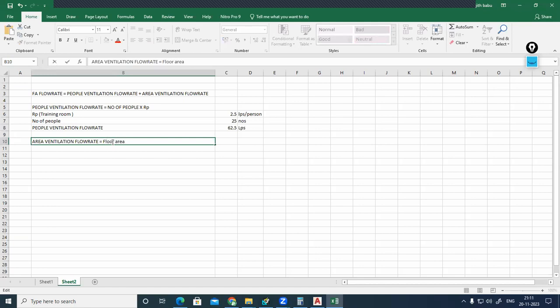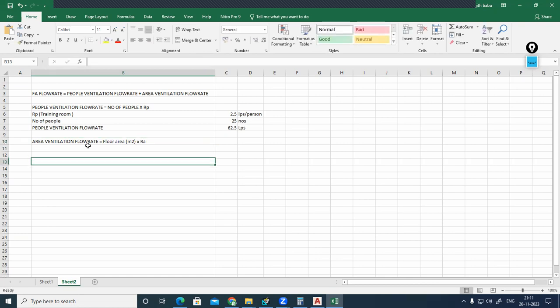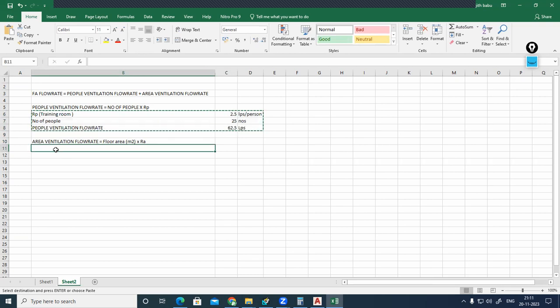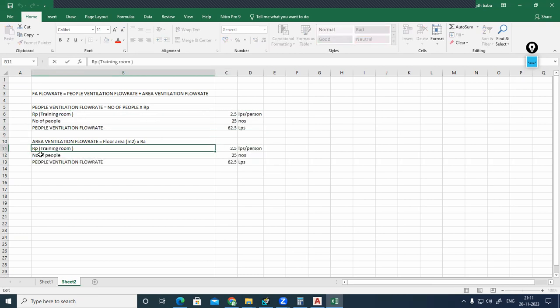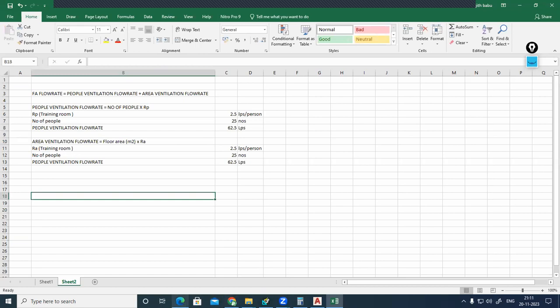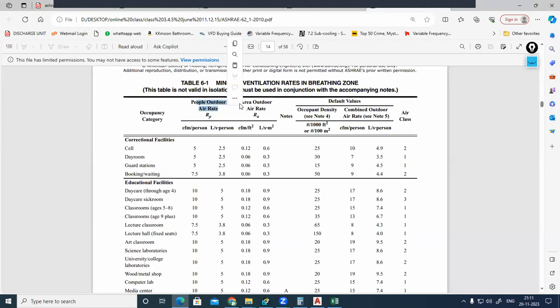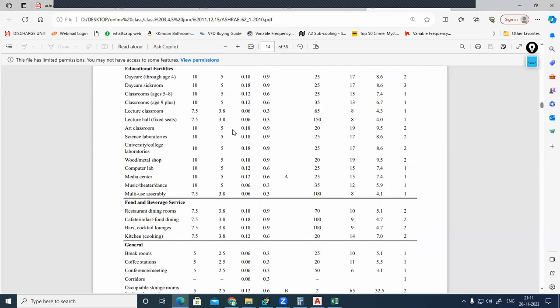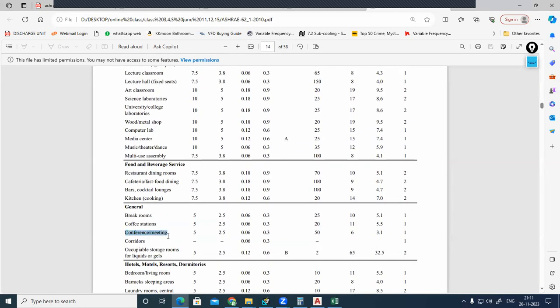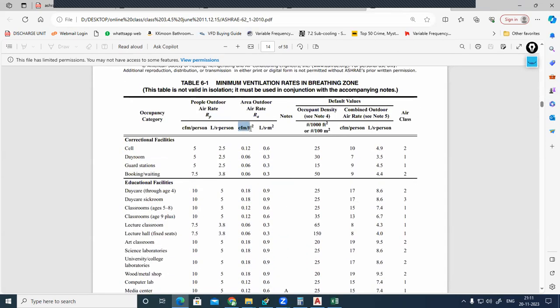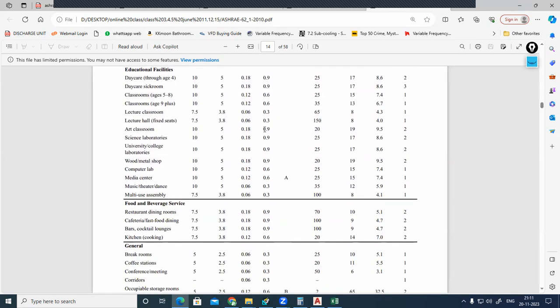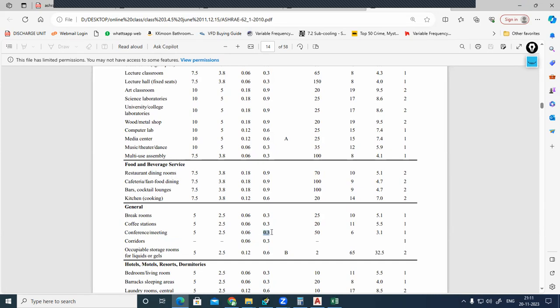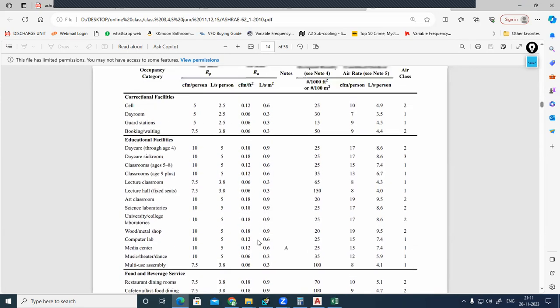Floor area that we are designing in meter square, multiplied by RA value. RA value. So, RA value, we can take from here. For example, this is not RP. RA value of training room, from the same table, you can find. Occupancy, people outdoor, area outdoor air rate, RA value. If you are coming to this one, a conference room or meeting room, CFM per square feet and liter per second per square meter. Since we are dealing with the SI unit, you can go for liter per second. Conference or meeting room, each meter square we should deliver 0.3 liter per second to maintain the indoor air quality.